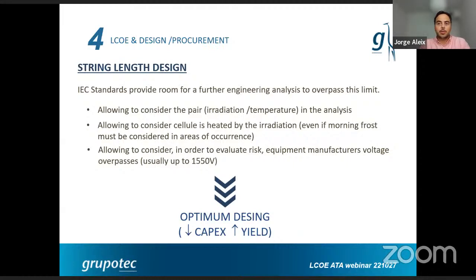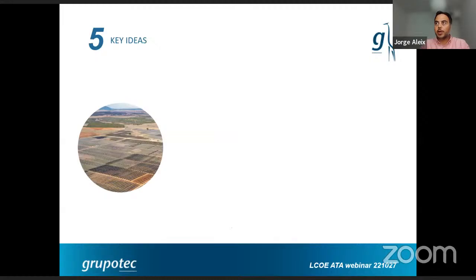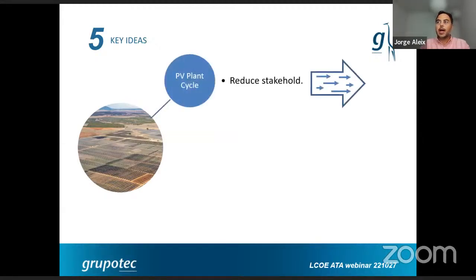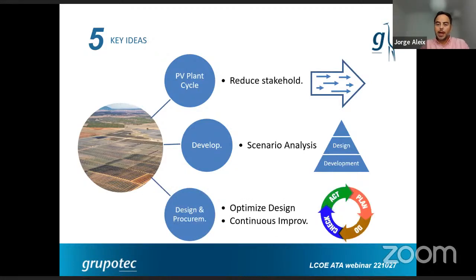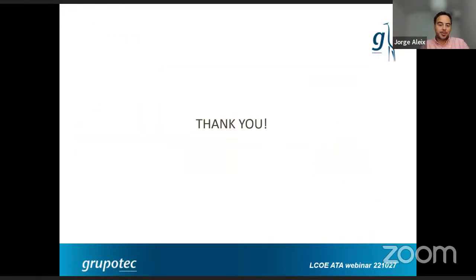With this analysis we can optimize CAPEX by getting the optimum string length, and increase yield by having strings operate at higher voltages — where most inverters have higher performance and cable losses are reduced. To summarize: consider the overall lifecycle in the LCOE; reduce stakeholders so everyone is aligned; take the development phase very seriously because the earlier you address it the more you can improve LCOE; and focus on design and procurement with continuous improvement of design and equipment selection.